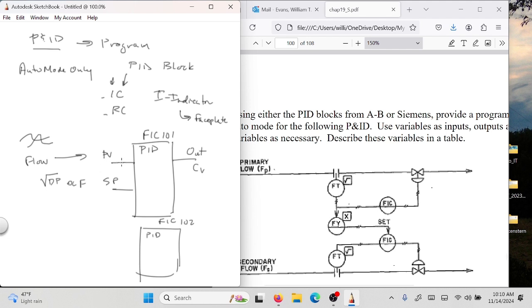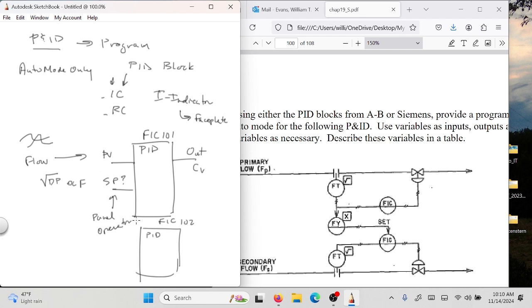Now I've given you what's going on with the PV, but where's the SP coming from if you don't see two things coming into the FIC? Any ideas? The set point is coming from the panel — from the operator. So if there's not two inputs shown, one of them is implied to be coming from the operator panel. The operator comes up to the panel, says 'give me so much flow,' and that's what that does.